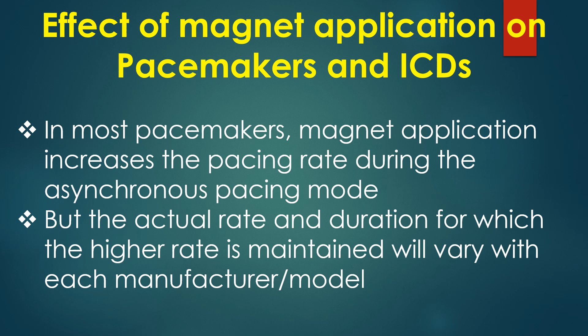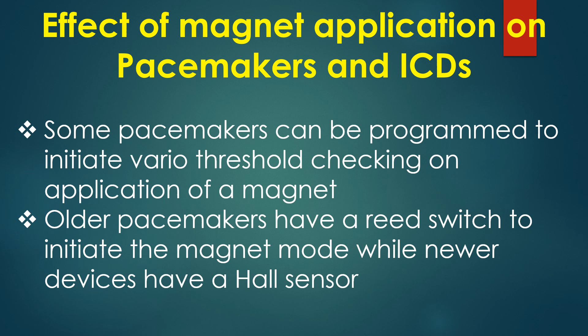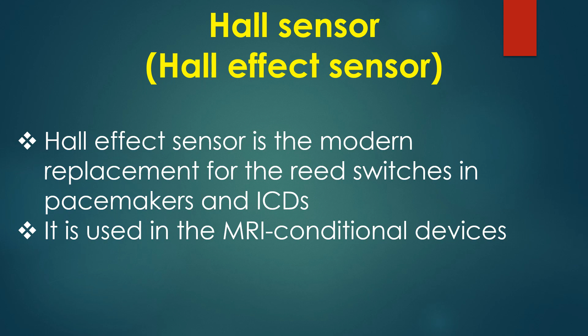In most pacemakers, magnet application increases the pacing rate during the asynchronous pacing mode, but the actual rate and duration for which the higher rate is maintained will vary with each manufacturer or model. Some pacemakers can be programmed to initiate vario threshold checking on application of a magnet. Older pacemakers have a reed switch to initiate the magnet mode, while newer devices have a Hall sensor. Hall effect sensor is the modern replacement for the reed switches in pacemakers and ICDs. It is used in MRI conditional devices.